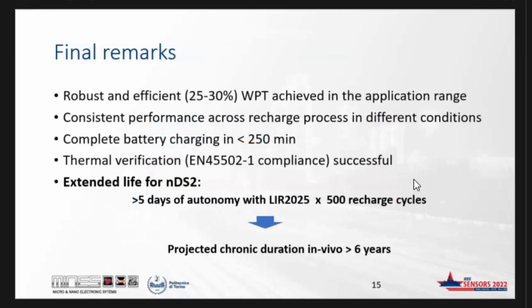To conclude, we demonstrated a robust and efficient wireless power transfer achieved across the intended application range, with efficiencies between 25 and 30%. We achieved consistent performance across the recharge process in different conditions. Complete battery charging is achieved in around 4 hours, and the thermal verification of the device according to the standard for animal tests is successful.